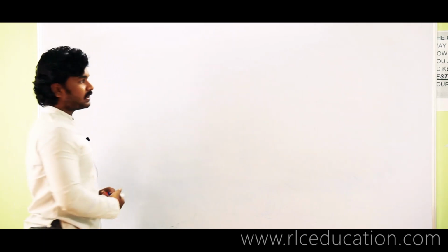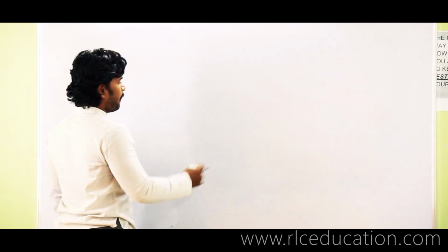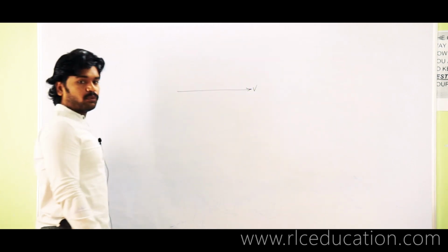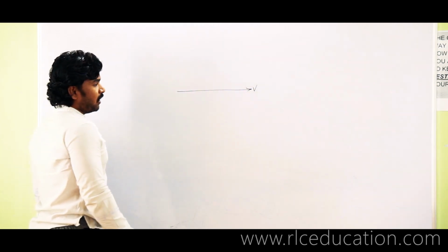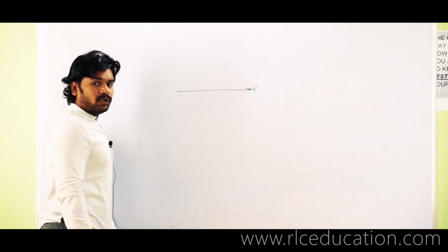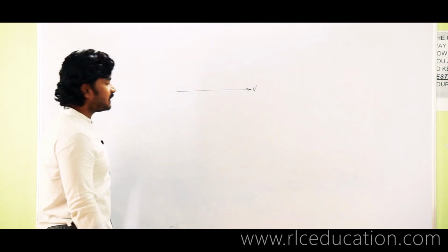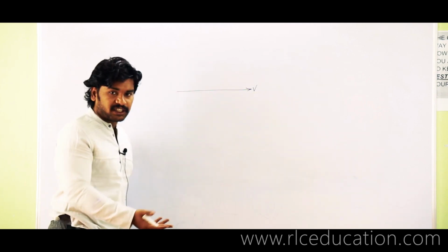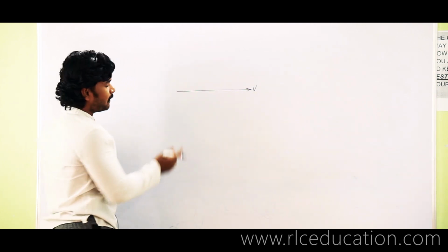Now let us see a case. In this case, I am having the voltage. This is the applied voltage and it is the polarizing quantity, therefore it is at reference. Now the current flowing through the voltage coil, because the voltage coil has some resistance and inductance, obviously the current flowing through the voltage coil in the directional unit will lag the voltage by some degrees.